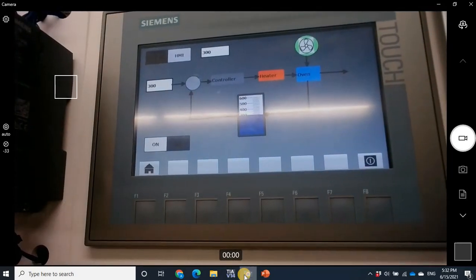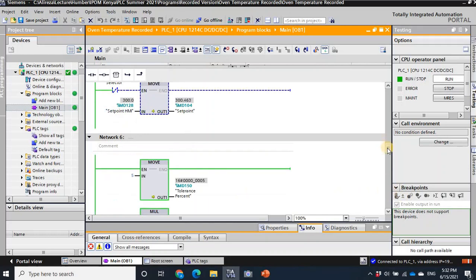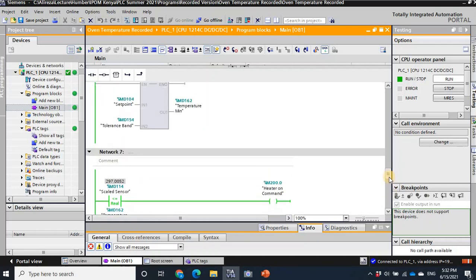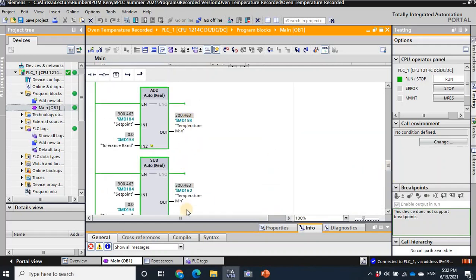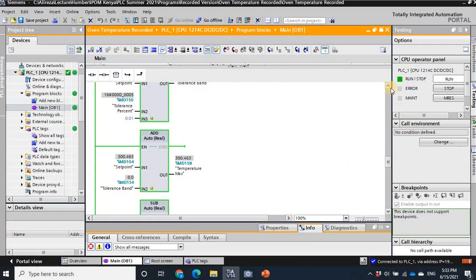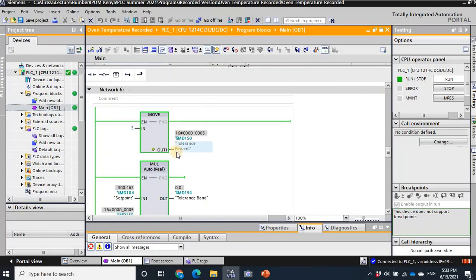There should be something wrong with this part — let's check it. Looking at the temperature max and temperature min, both of them show 300. The tolerance band is zero, but it should be five percent around the set point — approximately 15 degrees. Something is wrong with the tolerance band value.